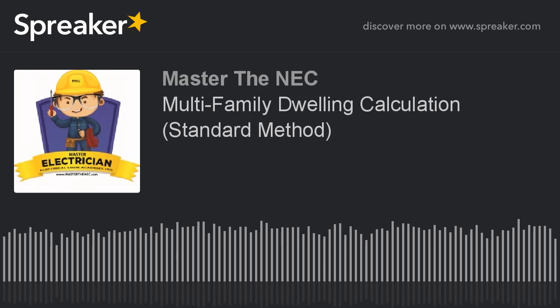So to see how that works out, you're going to go to 220.52(A) for the dwelling units, and you'll see that we're going to deal with the small appliance circuit loads first. These are the small appliance circuits that are required by 210.11(C)(1), and no less than 2 of them have to apply here. And when we're doing a calculation like this, it's 1,500 VA each. Now, what happens if I were to have a big house and I had 5 small appliance branch circuits in it? Then I'm going to have 1,500 for each one of those 5.